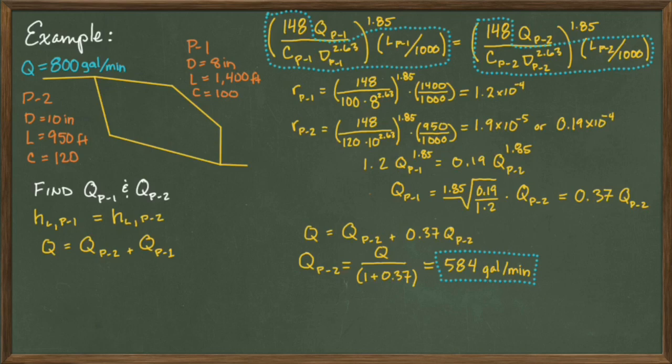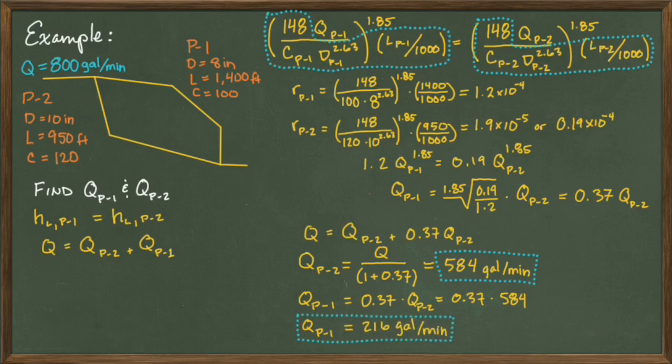Plugging that value back into our continuity equation, we get the flow rate in pipe 1 is equal to 0.37 times the flow rate in pipe 2, which is equal to 0.37 times 584 gallons per minute, or in other words, 216 gallons per minute for the flow rate in pipe 1.